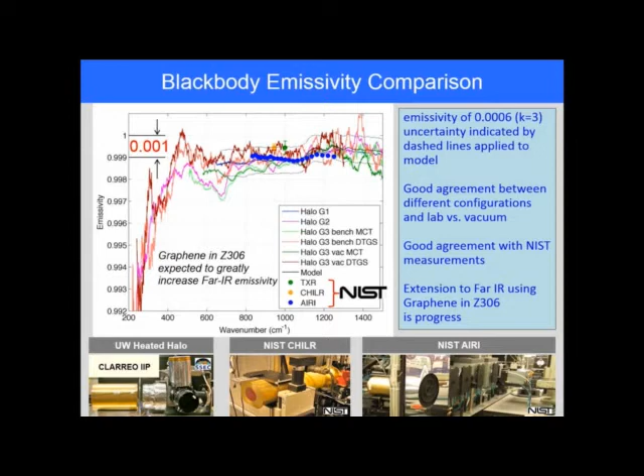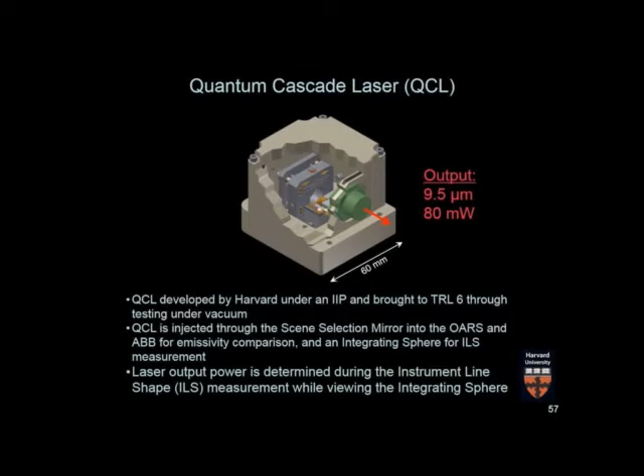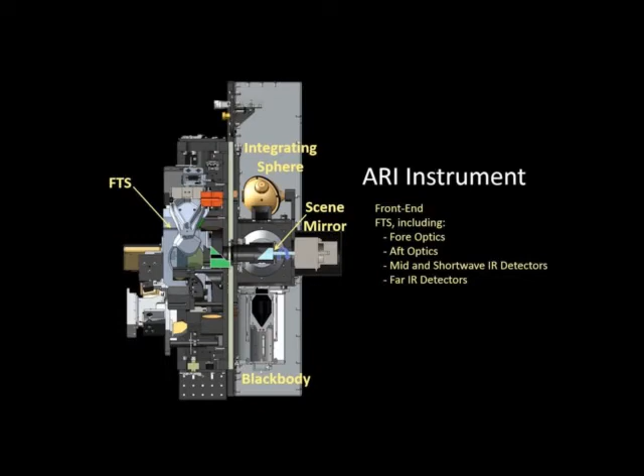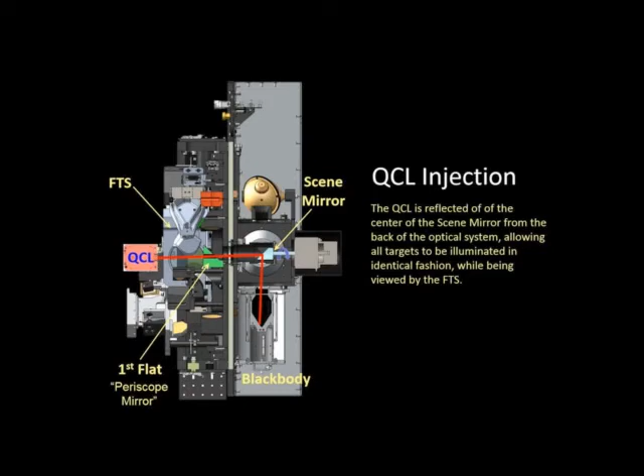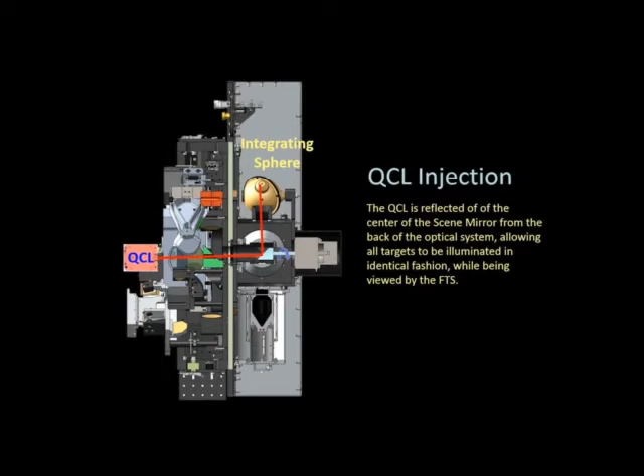Okay, so Joe introduced this. Harvard put together this quantum cascade laser, which enables 2 different measurements in our on-orbit verification. So we had a spectral emissivity that I just described. This one allows the emissivity of our black bodies to be made at the wavelength of the laser, and also to measure the instrument line shape. And this is a side view of the front end of our system, and that's a 45-degree mirror, and there's our interferometer back end. We inject this laser into our scene mirror. We can point it into this black body, and then it gets viewed by the interferometer. We can point it into an integrating sphere to do the instrument line shape measurement.